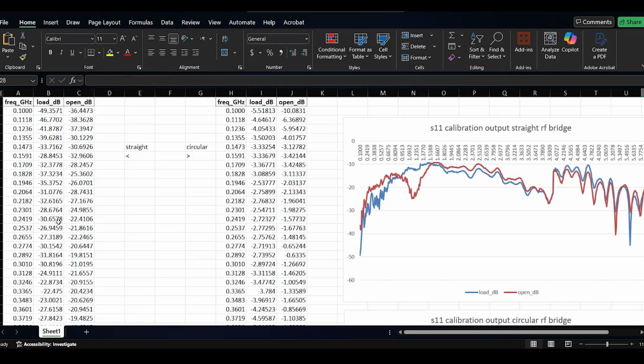This means that if I want to make the open equal to zero, because what calibration does after this point is say, okay, this is open. If the calibration is applied, I just want to make this zero, because when the open is connected, I have all the voltage reflected back. So this is zero, and it just offsets the other one, when the load is connected, to minus 10 dB, right? But you can see then the dynamic range I can get with this RF bridge is on the order of 10 dB or so.